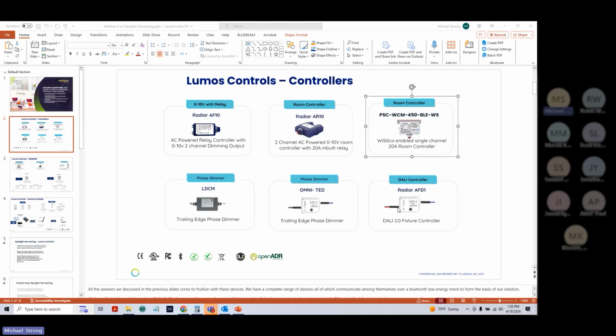The DALI controller, for those of you that don't know, is really great for emergency battery backup solutions here in the US. If you have a building, especially a legacy building, that has batteries in the lights, and even some of the new retrofits, we're still seeing it because we do a lot of submittals. We see the batteries being specified. If that's the case, we have a solution that will automate the emergency driver, rather than having to push a button for 30 seconds once a month and turning off the lights, running around and recording the results once a year for 90 minutes. We have a solution that will automate that process, keep building owners and facility managers or companies in compliance, and will be easy to validate for any safety authority that happens to show up asking for those records.